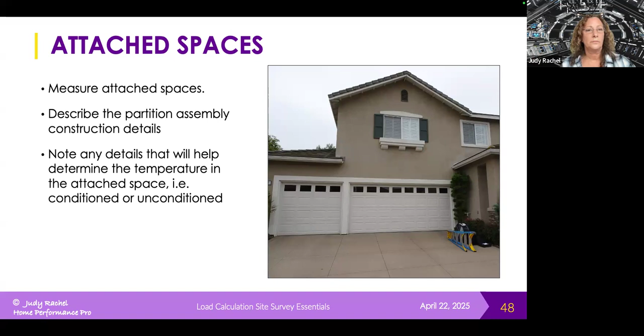You want to note any details beyond your measurements that determine whether there's a conditioned or unconditioned space on the other side. If you have any clues about the temperature in an unconditioned space, you can use that in your load calculation to help with the temperature difference across that assembly, which drives the heat transfer. Often you won't have that, so you'll have to make an educated guess, which the software helps you do.